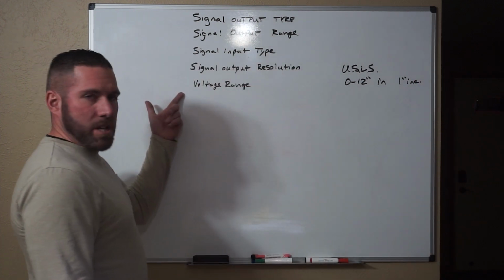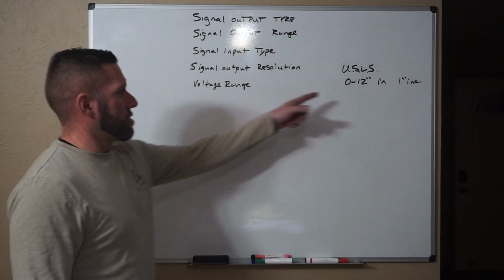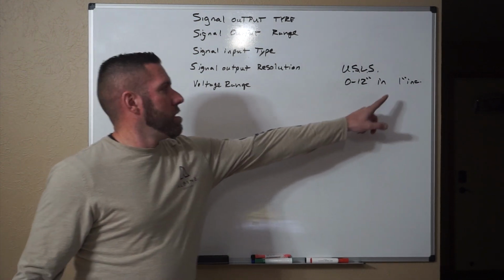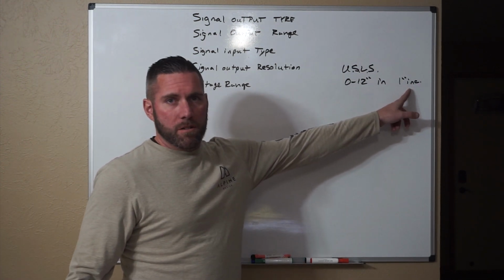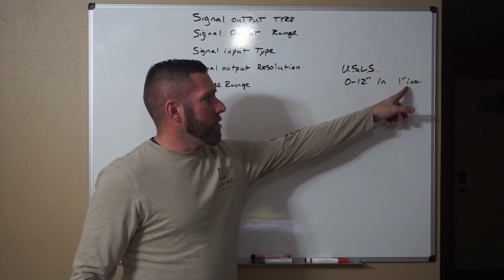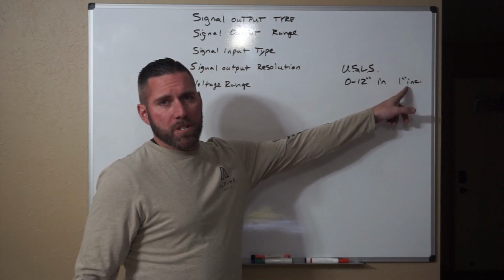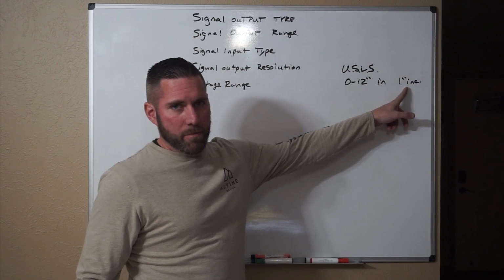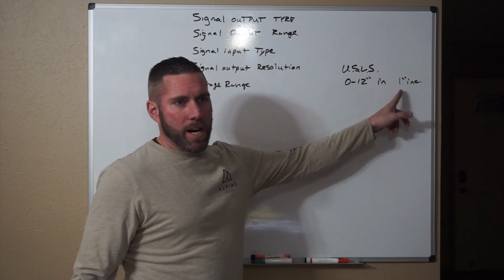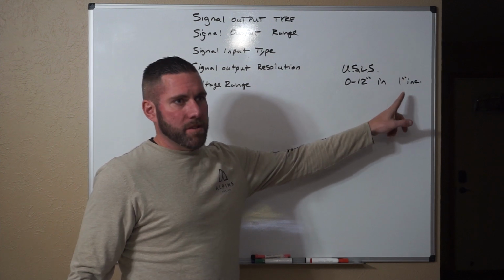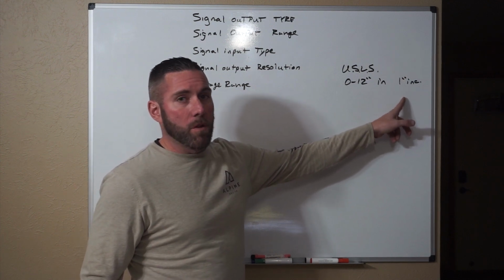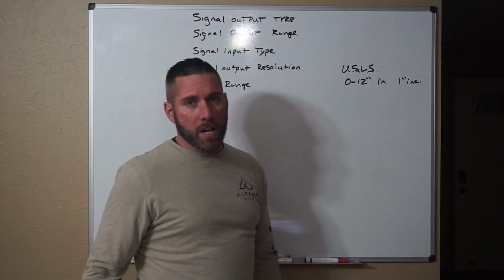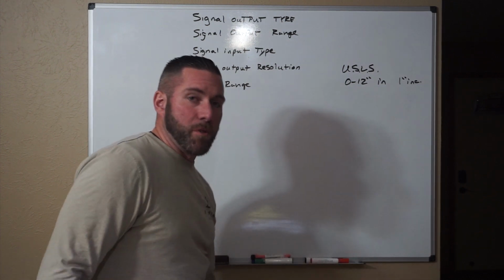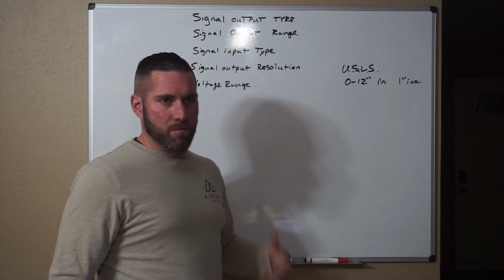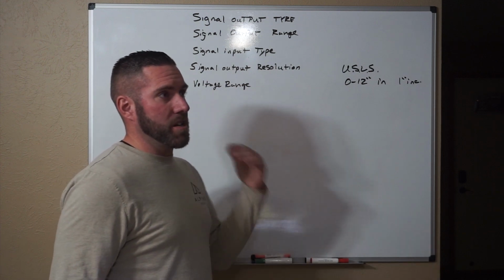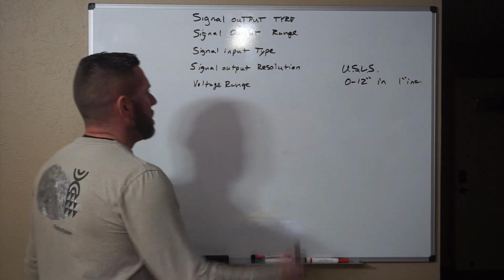So now we need all of these for an ultrasonic sensor in order to get that read at no less than a 1 inch increment. So if we go to measure 2, 4, 6, 8, 10, 12, that's not going to work, because at some point one of our highs, lows, or low alarms may go off based on this reading 1.5 when it's trying to read a 2. It's going to round down to the next significant point that it can actually measure.